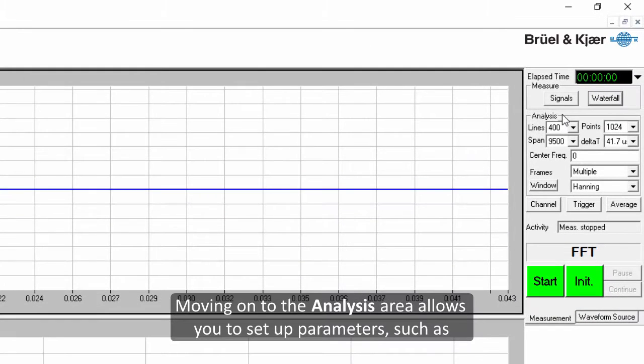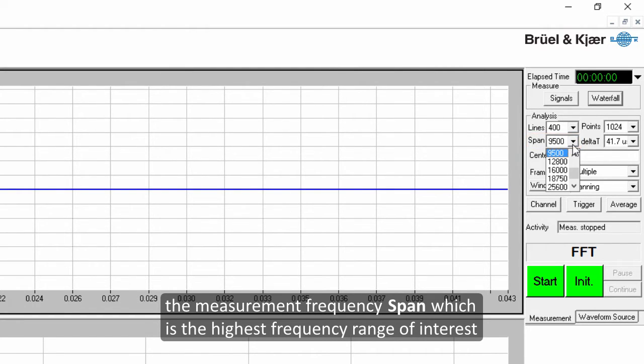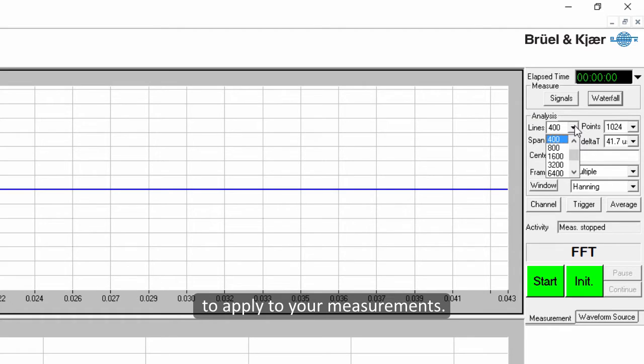Moving on to the analysis area allows you to set up parameters such as the measurement frequency span, which is the highest frequency range of interest, as well as the lines parameter, which is the number of FFT lines to apply to your measurements.